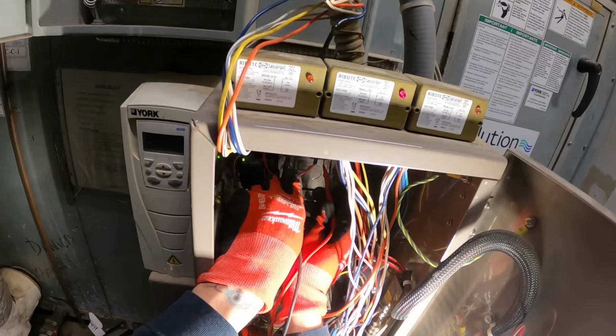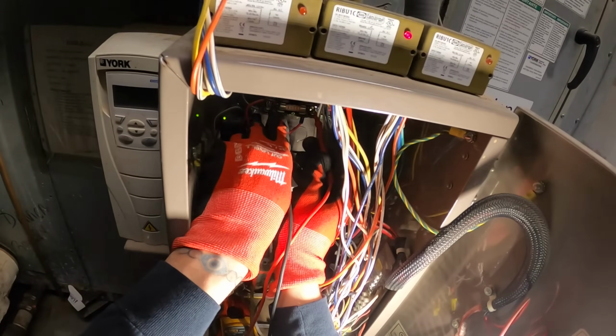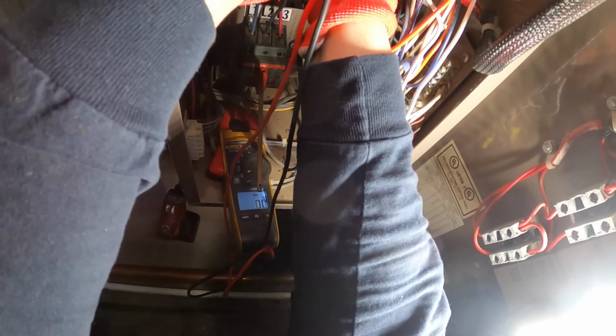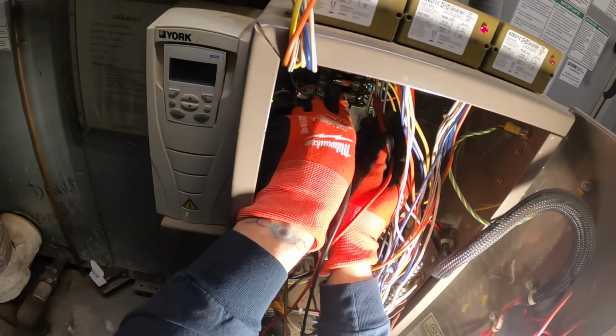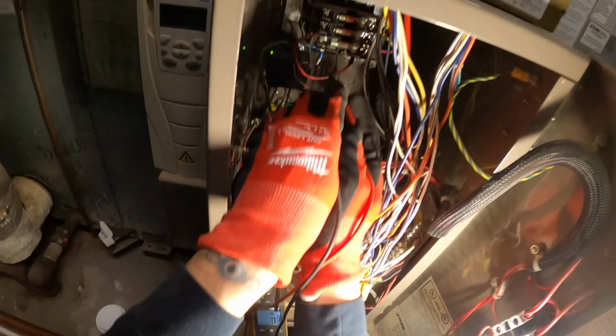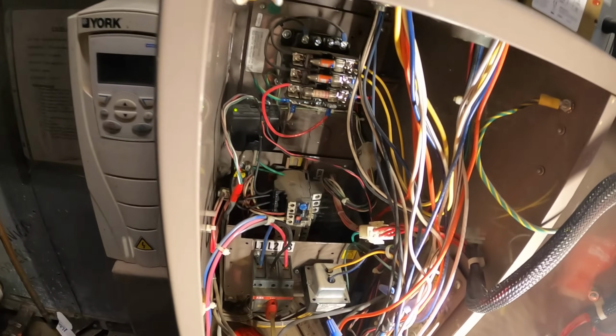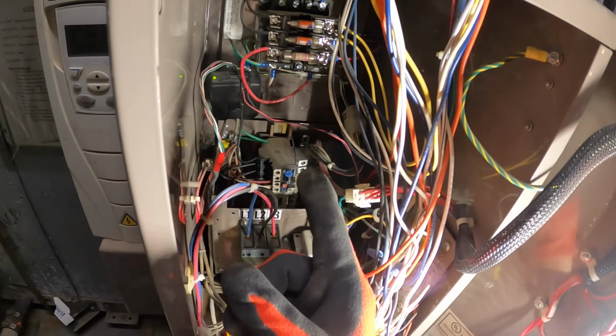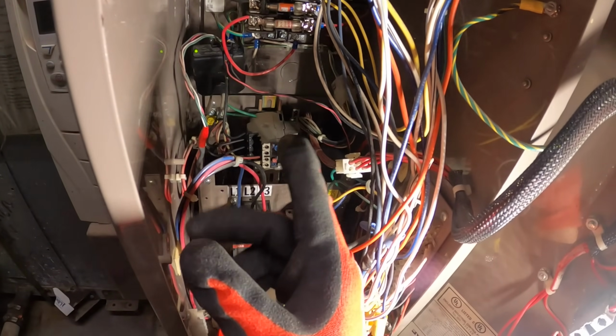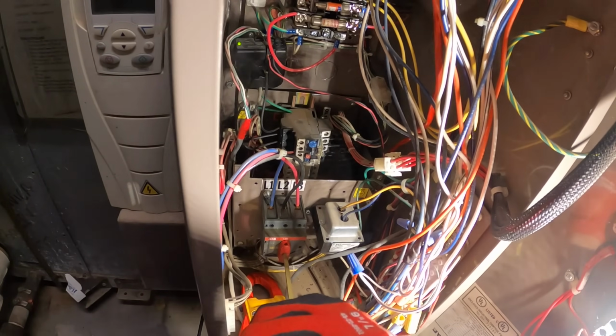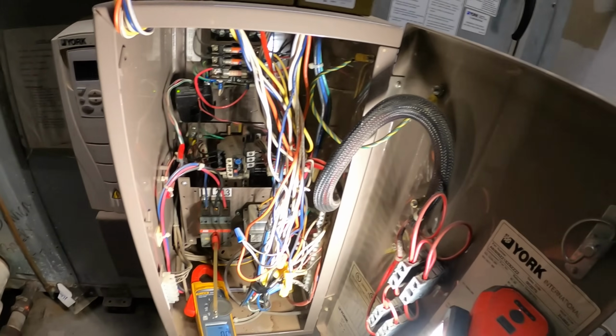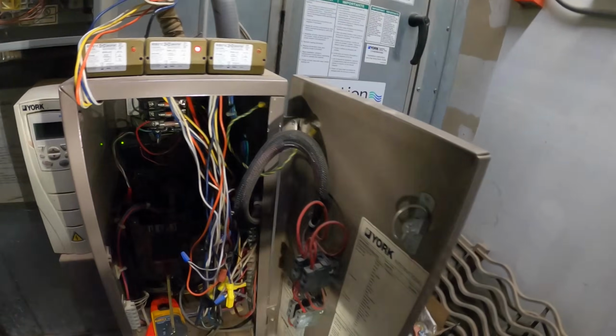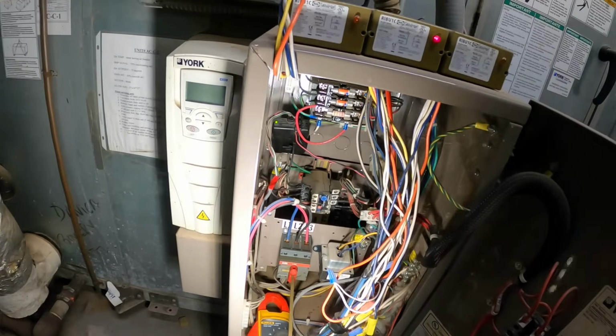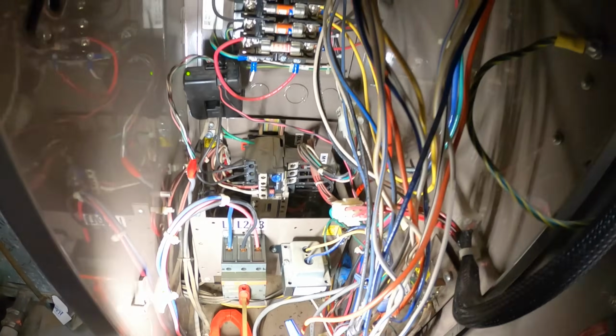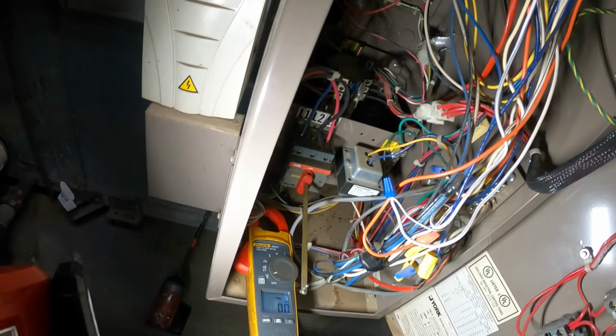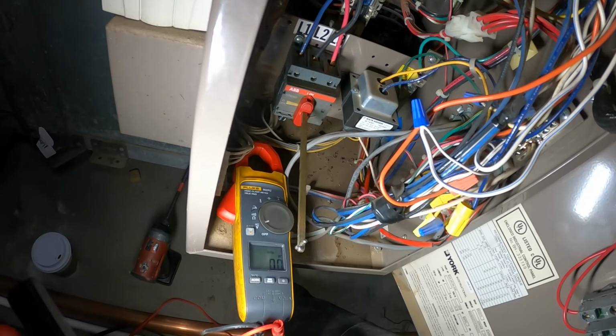I should have 0 volts across these fuses. Another way to check. Yeah, so power's passing through the fuses. The fuses are good. Got 120 on one side and 208 on the other. I'm gonna rule that out. It's something. Could these switches be bad and not turning on our motor starter? The thing is, I need to get in there. How can I take this out?